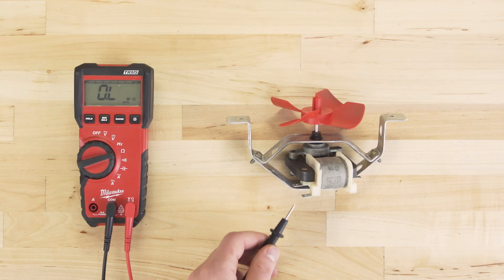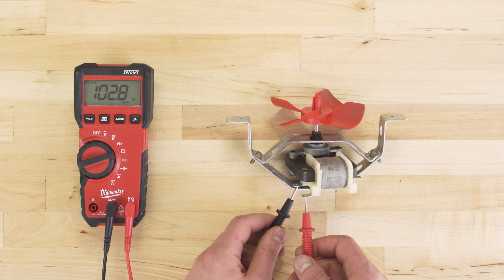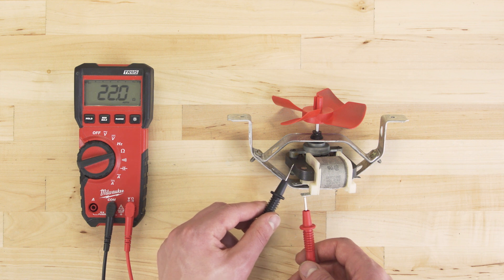Next, check the motor windings for continuity. Without continuity, there will be no magnetic field. As well, you can check to see if the motor is shorted to ground. Simply test from the terminals to any metal on the frame. If there's continuity, then the motor is shorted and will need to be replaced.